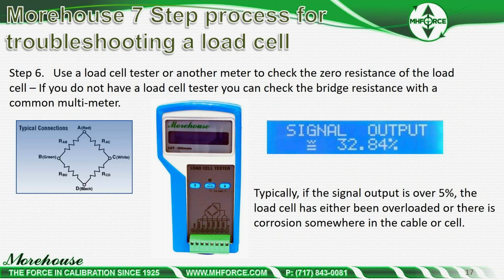On this particular one, the picture that I'm showing here is a signal output of 32.84%. We want that number to be under 5. So if the signal output is over 5, the load cell has either been overloaded or there is corrosion somewhere in the cable or cell. Typically, we're going to see most of the time that it's been overloaded at a signal equivalent of over 5%, at which point you're almost going to have to replace the load cell.